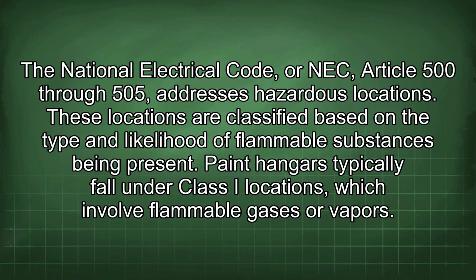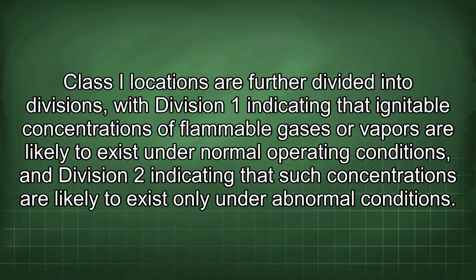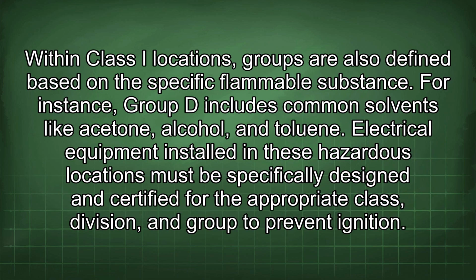The National Electrical Code, or NEC, Article 500 through 505, addresses hazardous locations. These locations are classified based on the type and likelihood of flammable substances being present. Paint hangars typically fall under Class I locations, which involve flammable gases or vapors. Class I locations are further divided into divisions, with Division 1 indicating that ignitable concentrations of flammable gases or vapors are likely to exist under normal operating conditions, and Division 2 indicating that such concentrations are likely to exist only under abnormal conditions. Within Class I locations, groups are also defined based on the specific flammable substance. For instance, Group D includes common solvents like acetone, alcohol, and toluene.